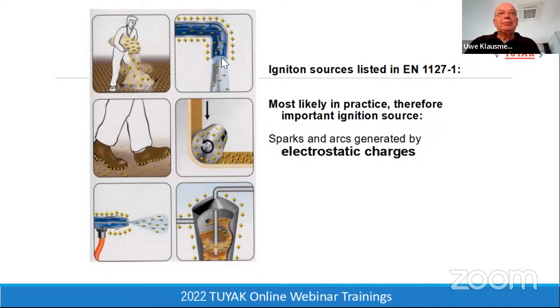Also here, this pipe is causing electrostatic charge because we have a liquid, maybe a non-conductive liquid, going through the pipe, and then the wall of the pipe will also get loaded by electrostatic charge. And you can imagine, as soon as this is a plastic material, then the charge will be very big because earthing is not possible with insulating plastic material. Insofar, it's better to have a metallic pipe here.